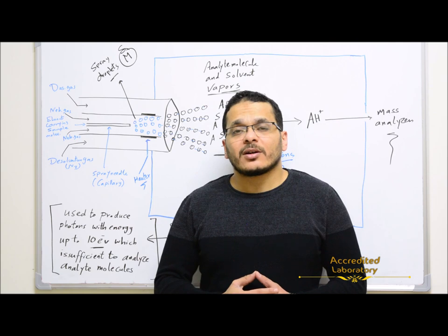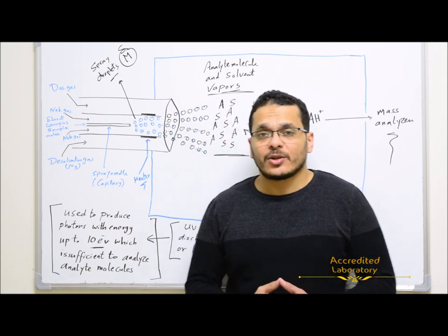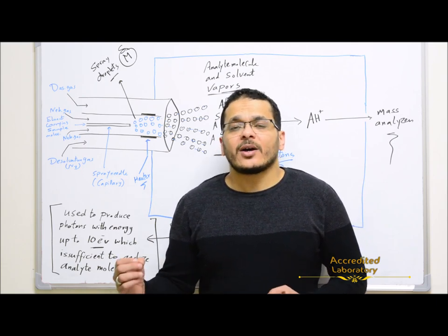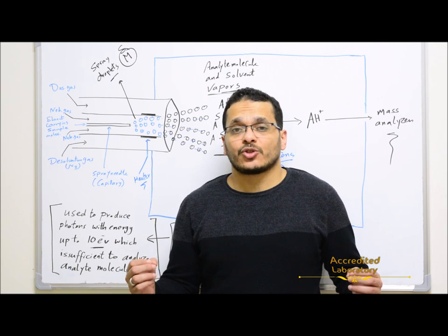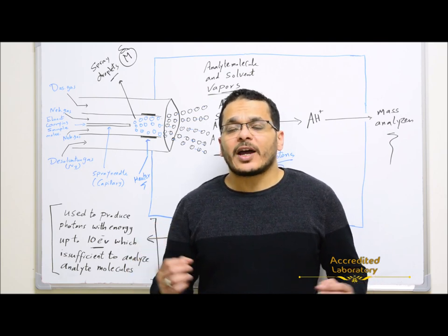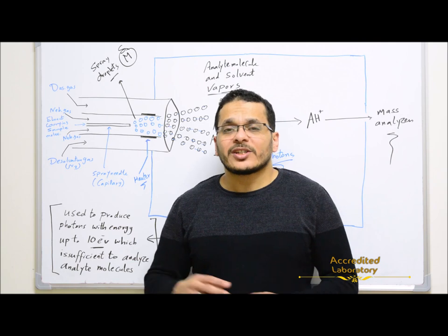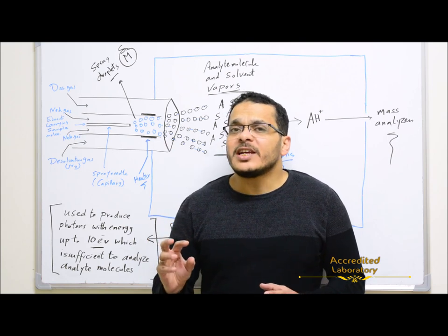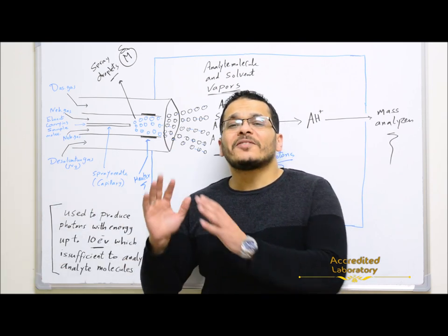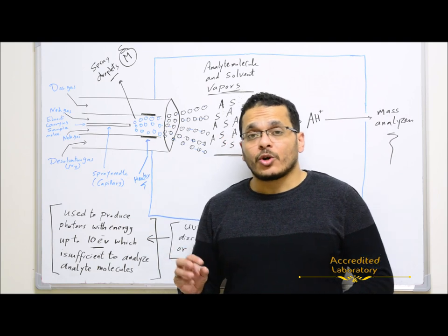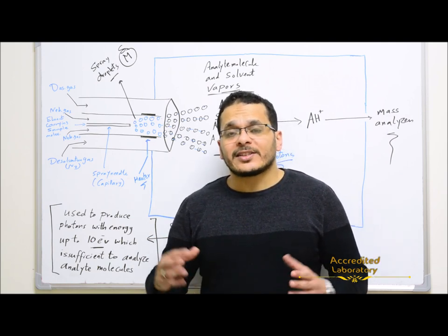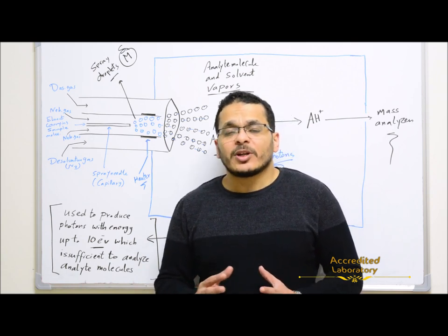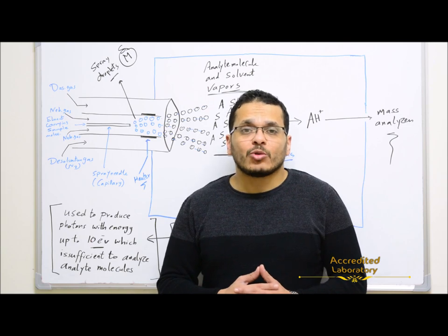In today's lecture I will start with atmospheric pressure photo ionization ion source, which is less popular when compared to electrospray ionization or atmospheric pressure chemical ionization ion source. It is a type of soft ionization technique where samples will be ionized in the ion source to get a precursor ion, which will be transferred to the mass analyzer to be fragmented in Q2, the quadrupole collision cell, to get product ions. Samples will be ionized by the photons generated by the UV light of the krypton lamp.